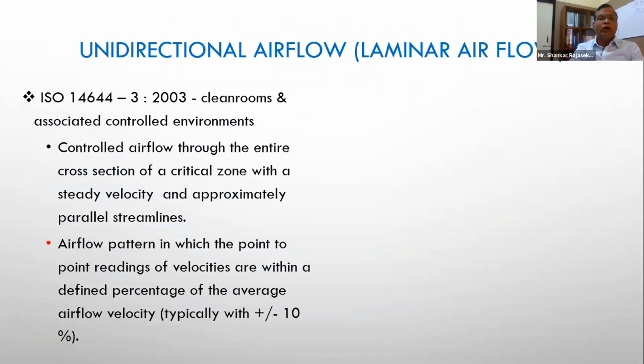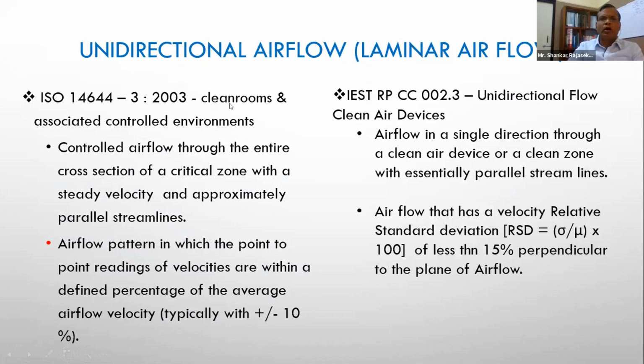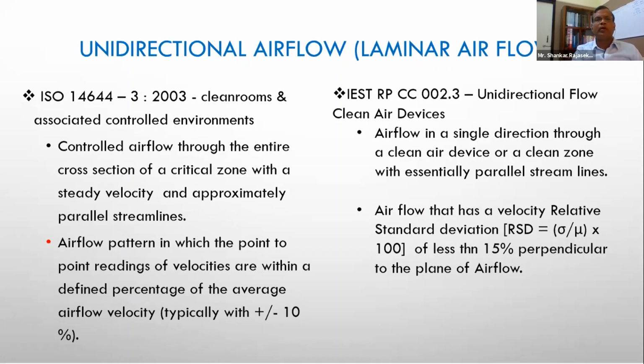So I am giving the definition of what is unidirectional flow, because, unfortunately, sorry to say this, many of the operating rooms which are supposed to be working as unidirectional airflow do not work as a unidirectional airflow theater, for several reasons, of course. So I thought I better put down what the definition would be. There are two standards which give an engineering definition for airflow. This ISO standard talks about velocity variation within plus or minus 10% from the average across the supply air diffuser. And this standard talks about an airflow that has a velocity relative standard deviation of less than 15%. If you do it rightly, you can actually get less than 5% relative standard deviation. And that will be a really nicely performing operation theater.